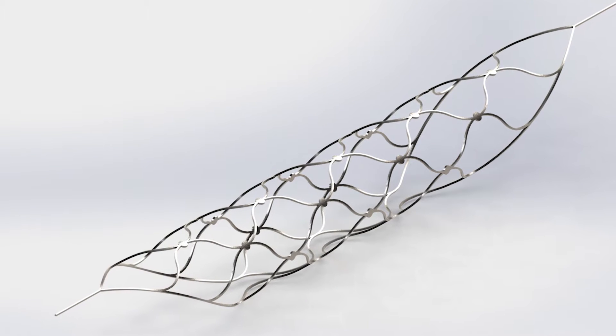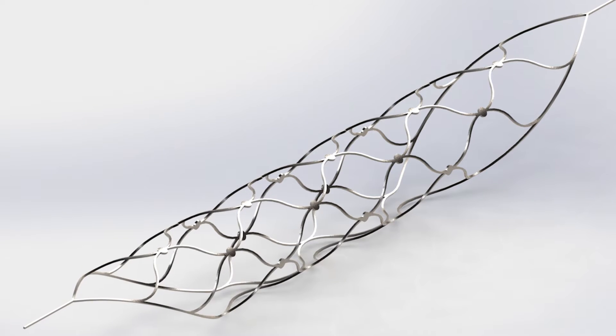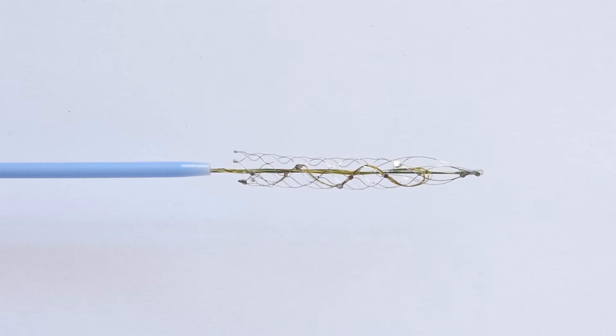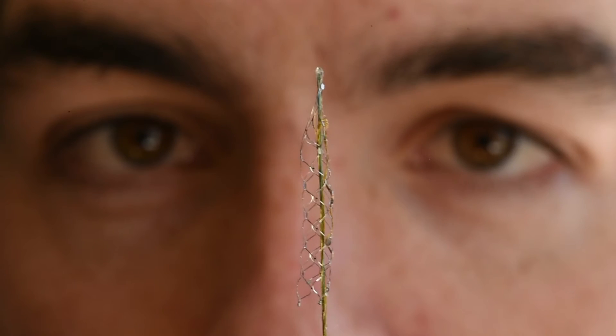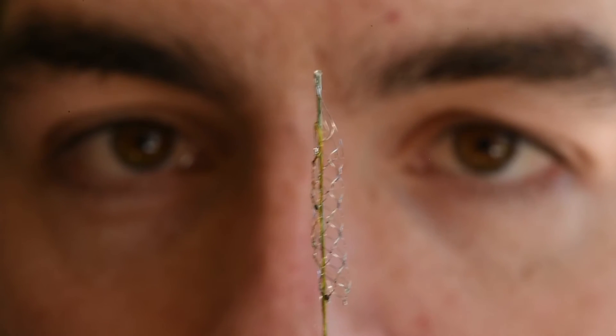One of the main challenges was to enable a device that was flexible enough to get around the blood vessels as well as strong enough to be pushed through the tube required to deliver it. The device is made out of nitinol, a nickel-titanium composite that enables it greater resilience when being flexed and compressed over other more commonly used materials, which allows us to deploy it through a very small catheter and expand it to a larger size when in the blood vessel region of interest.